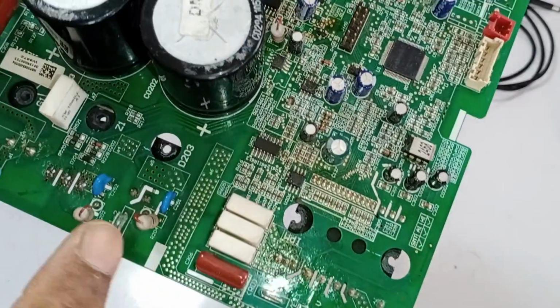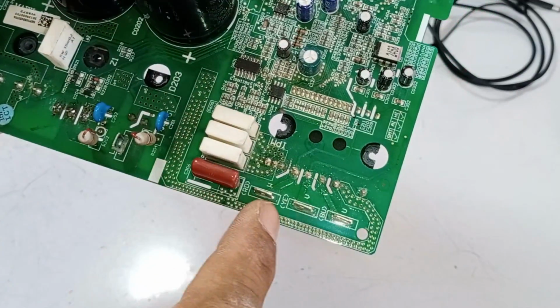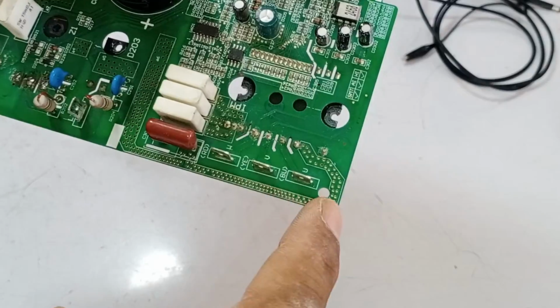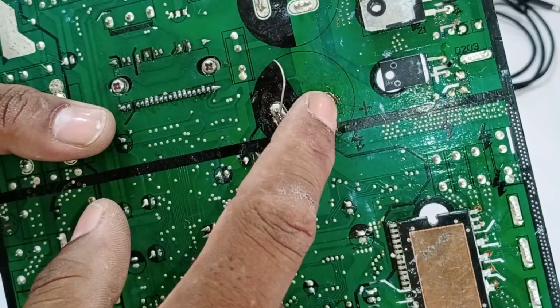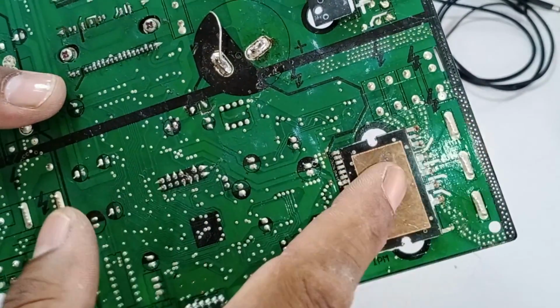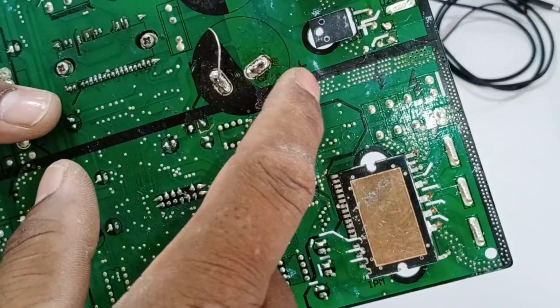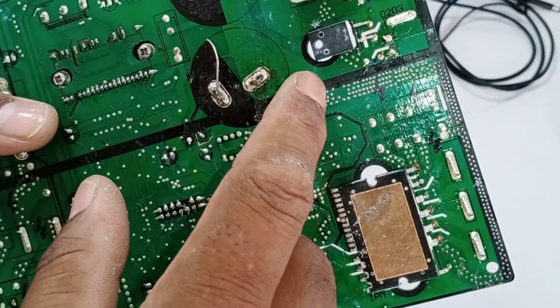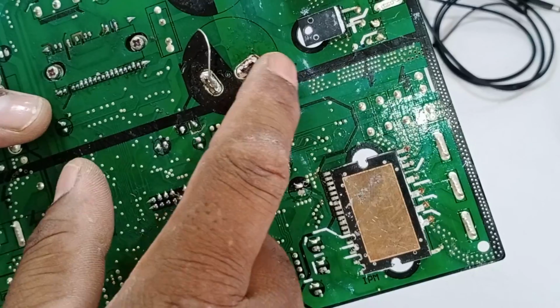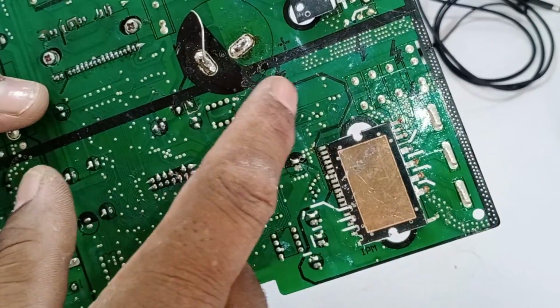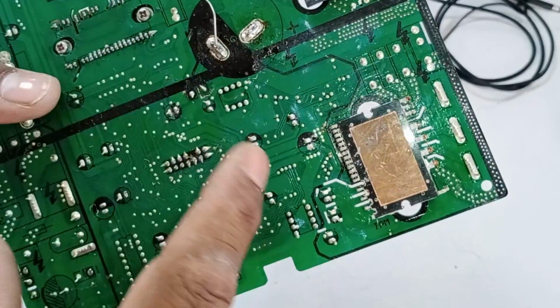Other than this, the PL could be shown due to this bus bar. This trace over here is known as a bus bar. This is the negative, and this is the positive moving from the capacitor, which is moving towards the IPM. If the print of the bus bar has a slight crack, which prevents the current from flowing properly through its traces, then the PL error will be displayed on the unit. So, these are the faults that could cause the PL error code in the unit.